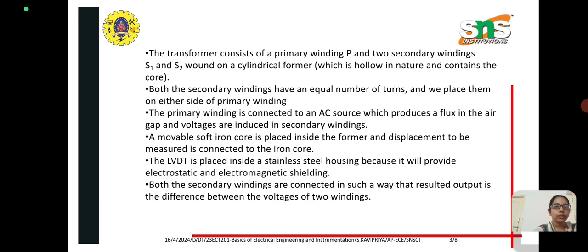A transformer consists of a primary winding and two secondary windings, which are wound on a cylindrical former. Both the secondary windings have an equal number of turns and we place them on either side of the primary winding. The primary winding is connected to the AC source, which produces a flux in the air gap, and voltages are induced in the secondary winding. A movable soft iron core is placed inside the former and the displacement to be measured is connected to the iron core. The LVDT is placed inside a stainless steel housing because it will provide electrostatic and electromagnetic shielding.